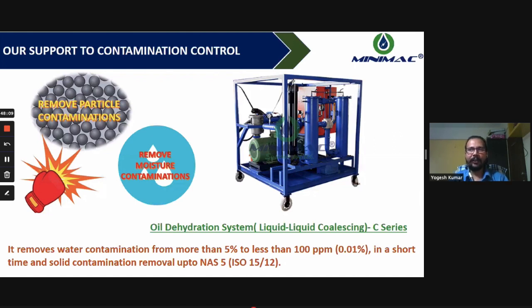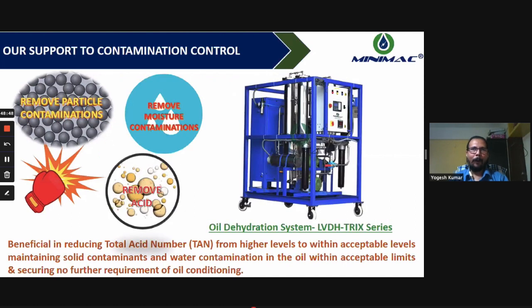So we have demonstrated this in our lab. We have a separate R&D lab. From 50,000 ppm to 500 ppm within 1 hour, at the rate of 100 lpm, less than 500 in 1 hour. We did it, and we are very confident we can support you if you need this, or we can propose it to you. Again, this is an oil dehydration system.